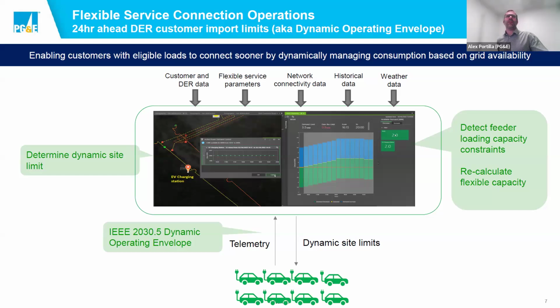This new customer, signed up for our Flex Connect program, is able to receive that signal. Our DERMS combined with our advanced distribution management system, ADMS, performs day-ahead hourly forecasting of available capacity on the circuit, and communicates that to customers as what's often called a dynamic operating envelope, using a standard protocol, IEEE 2030.5, giving the site day-ahead hourly limits.